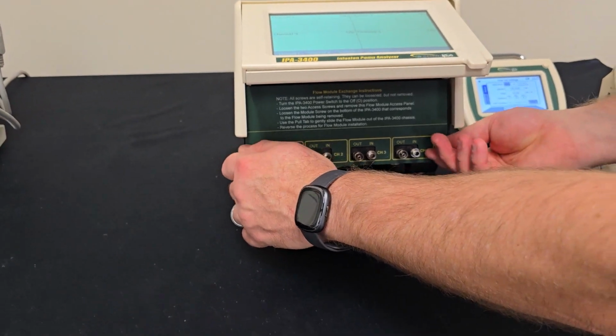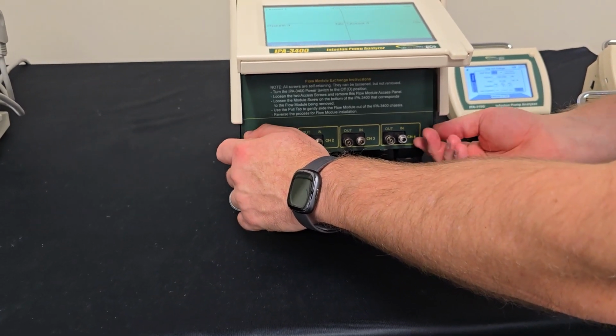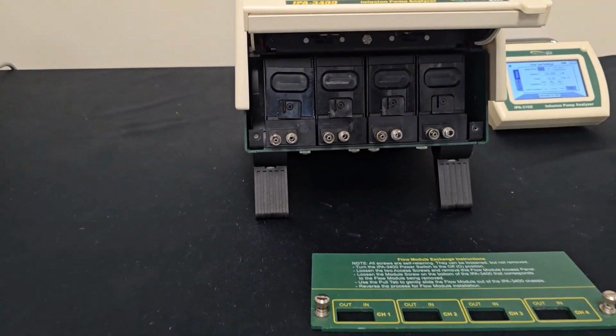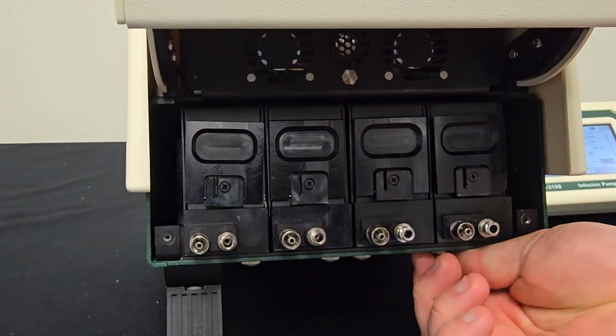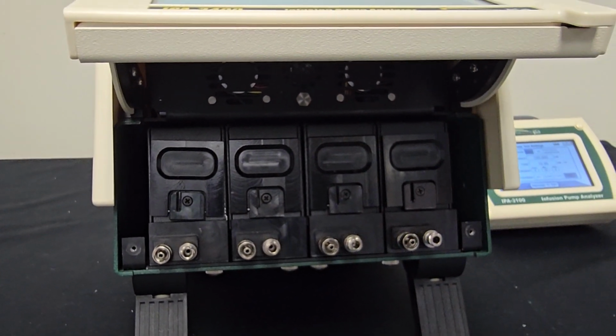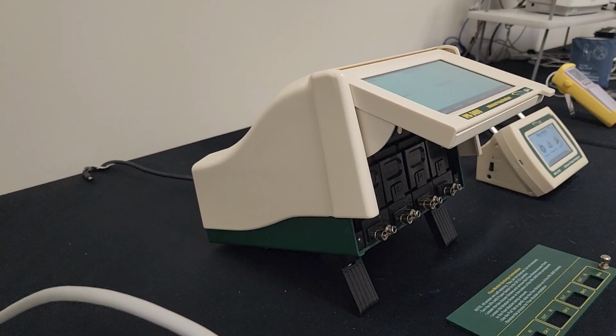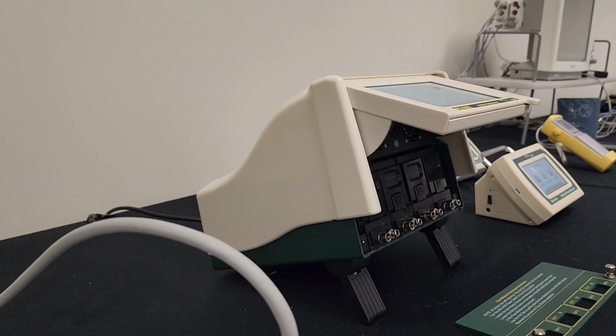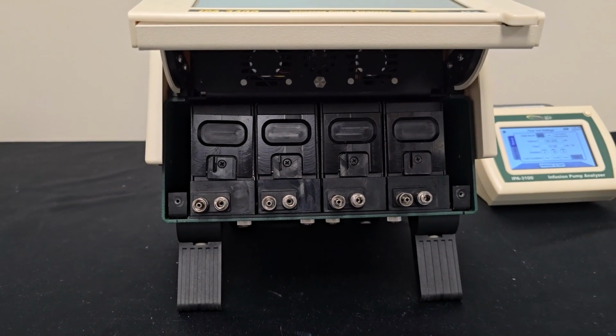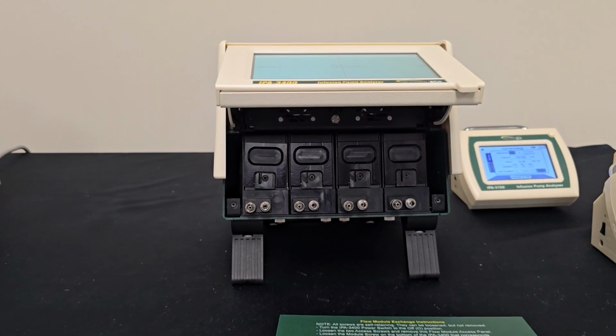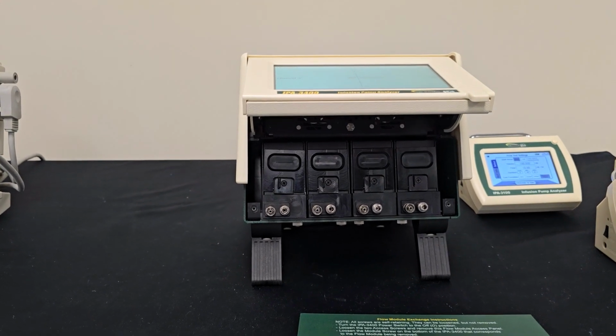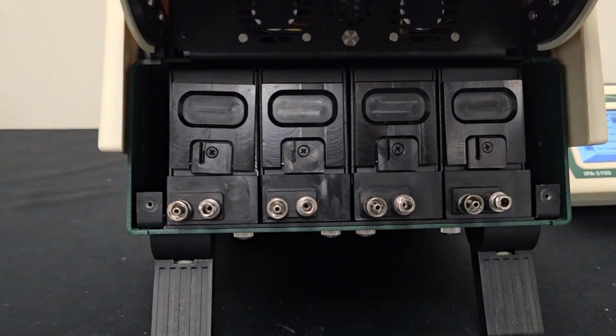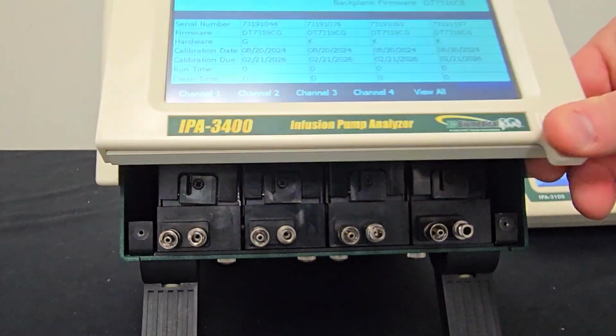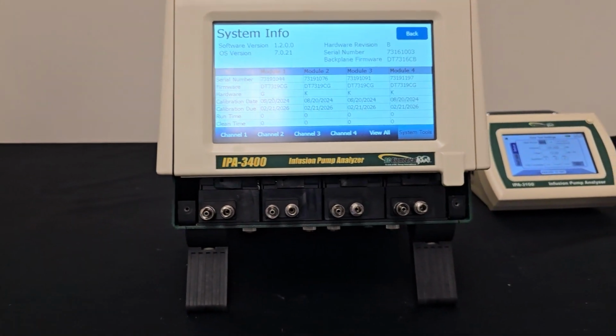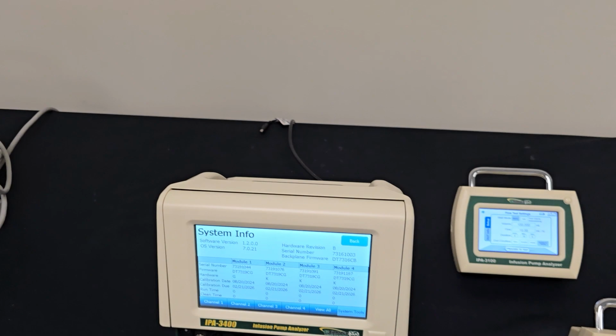And then these are also easily removable for calibration or maintenance. That way, if you have one channel that's due for calibration, you can just unscrew that from underneath and pull it out and send it in for cal. And you can still be testing with your other channels. Right. Each of those modules work independent of each other. And so if you take one of the modules out, the remaining modules are still functional. And they're calibrated independently. Wow. Okay. So you don't have to send the whole unit in for a calibration. That is correct. All of the calibration is stored by channel in the module itself. That's very cool.